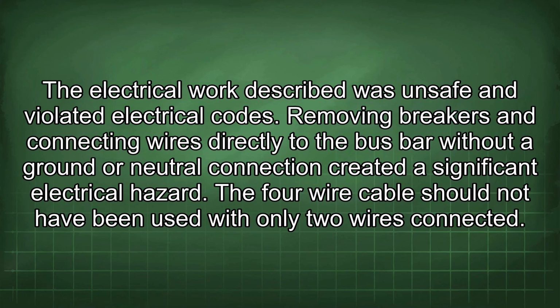The electrical work described was unsafe and violated electrical codes. Removing breakers and connecting wires directly to the bus bar without a ground or neutral connection created a significant electrical hazard. The 4-wire cable should not have been used with only 2 wires connected.